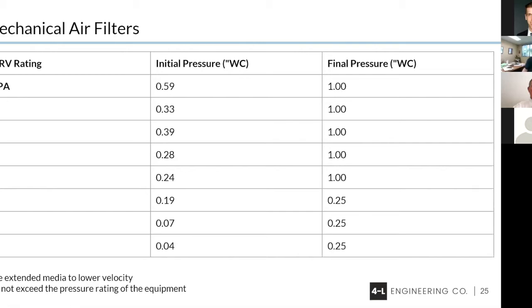If I move up to a MERV 13 from a MERV 1, you'll see that the initial pressure drop there is 0.39. That is a big change in the resistance across the filter. So again, this is why some of these air conditioning units that we have will not work with this MERV 13. Next slide.